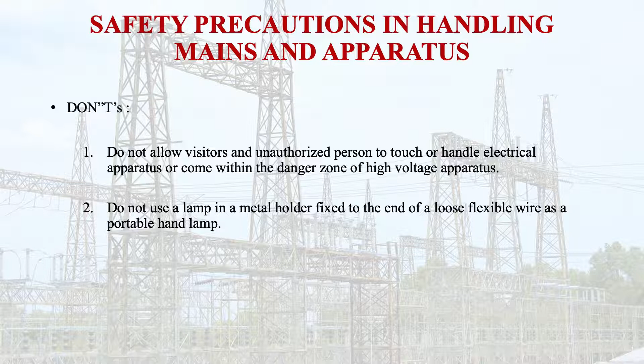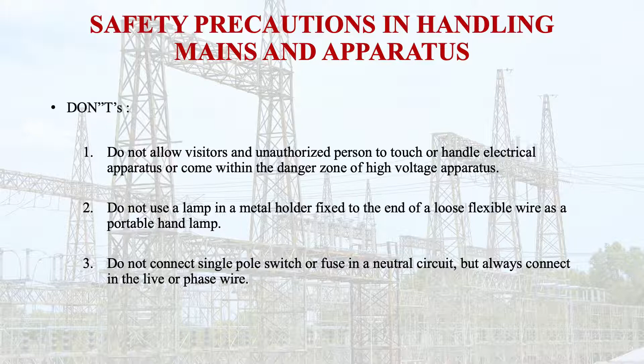Do not connect a single pole switch or fuse in a neutral circuit, but always connect it in the live or phase wire. So that means the fuse should be connected only on the live side, the phase wire side. It should not be connected in the neutral side, which may be earth. Learners, do not renew a blown fuse until you are satisfied as to the cause and have rectified any irregularity. And other safety precautions: do not use copper wire as a substitute for the fused wire.